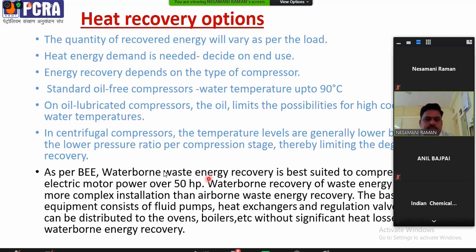As per BEE, waterborne waste energy recovery is best suited to compressors with electric motor power above 50 HP. If you install a water heat recovery system below 50 HP, we will not get a good payback period. Waterborne recovery requires a more complex installation, obviously, because we need a water pump and a heat exchanger, compared with airborne waste heat recovery. Heat can be distributed to ovens. If you take away heat through air, we can use it in ovens. If it is water, we can use it in boilers.